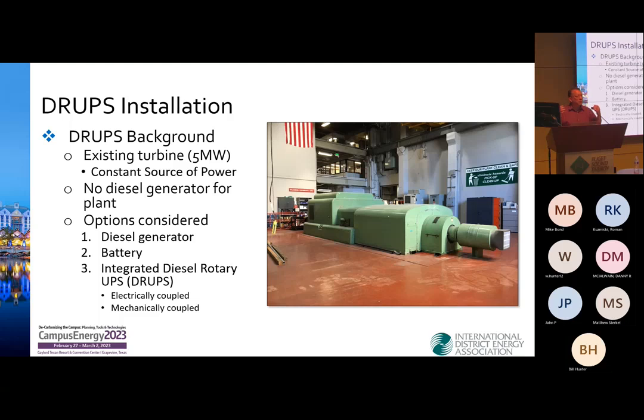So if the Seattle City Light died, which is rare, but they do once in a while, the turbine would be running, we would island the power plant, and we would just ride through and continue to operate. But it only works when the turbine generator is running. And again, going back to the 3, 4, 5 months a year it wasn't running was a risk we can't take. So we evaluated, do we do the traditional diesel generator route, which even though the plant in the video, you might have noticed, like we have 10 megawatts of diesel generation in the plant, but none of it was dedicated to the plant.